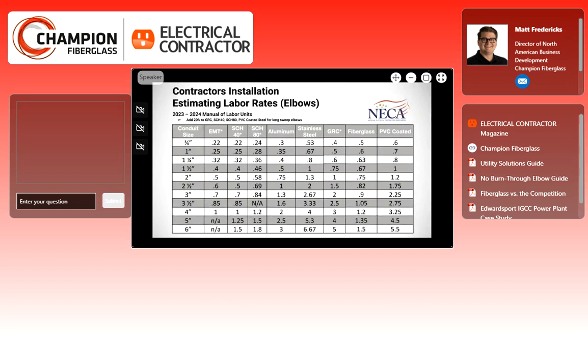Elbows follow the same suit, and it's important to note that on this chart, certain conduit types and sizes indicate savings for underground elbow construction as well as conduit construction. For longer radius sweeps, with the exception of fiberglass, you actually add 25% to the labor for those. Fiberglass, being lighter, will actually save you time in the long run for installation.